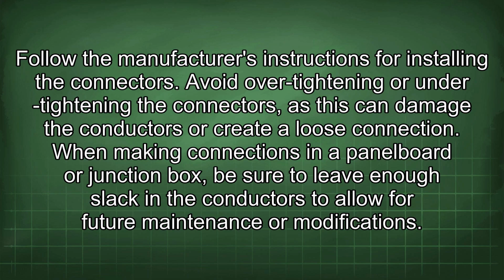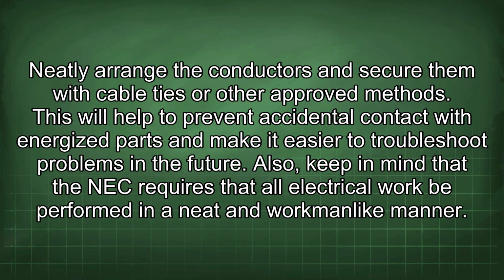When making connections in a panel board or junction box, be sure to leave enough slack in the conductors to allow for future maintenance or modifications. Neatly arrange the conductors and secure them with cable ties or other approved methods. This will help to prevent accidental contact with energized parts and make it easier to troubleshoot problems in the future.